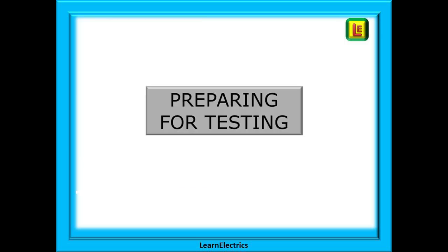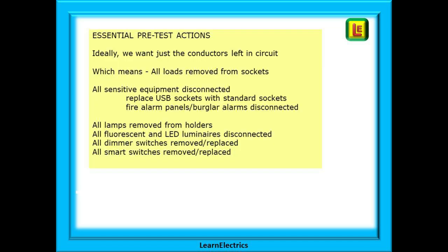We can't just turn up on site and start testing though. We must prepare the installation for testing and this is where experience and practice are essential. The actual preparation is easy but there are a lot of things to think of. With practice you will begin to do these things automatically. Ideally we want just the conductors left in the circuit — it is the conductor insulation that is being tested. We are testing there are no cuts or nicks, no nails through the cable or corroded and degraded insulation.